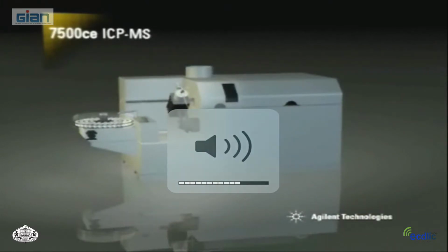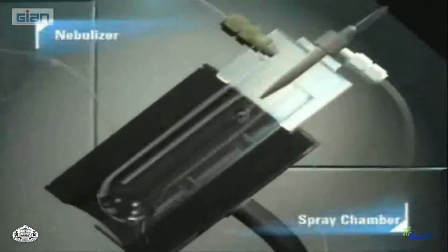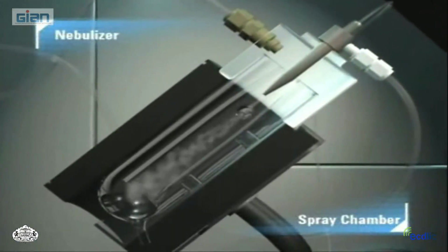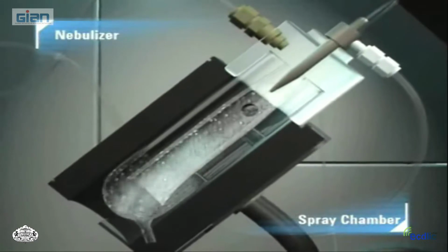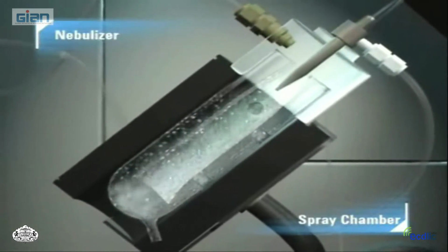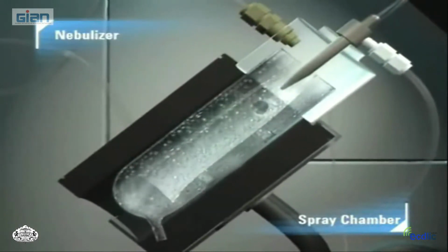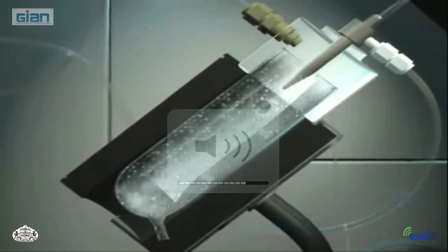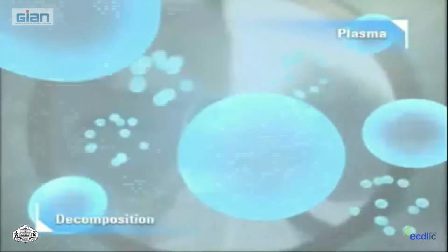Follow the journey a sample takes from its sample vial through the ICP-MS to the detector. Sample is pumped from the sample vial into the nebulizer, where it is mixed with argon gas to form an aerosol. Larger droplets are removed from the sample aerosol as it passes through the cooled spray chamber, and the fine aerosol is swept into the central channel of the plasma.